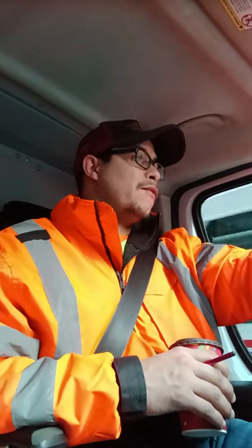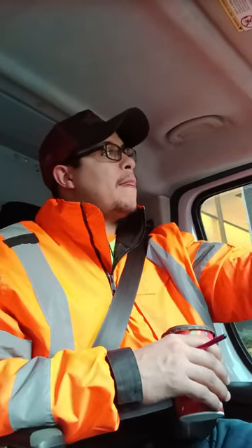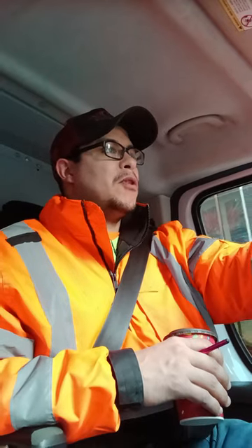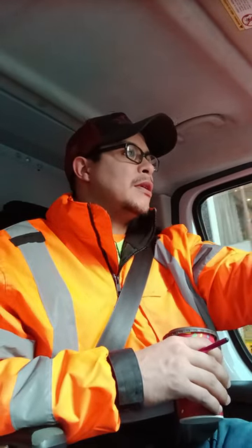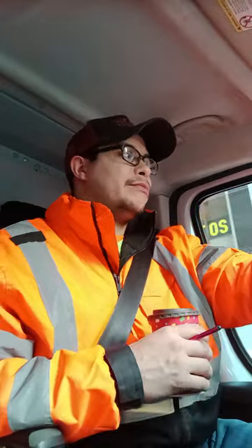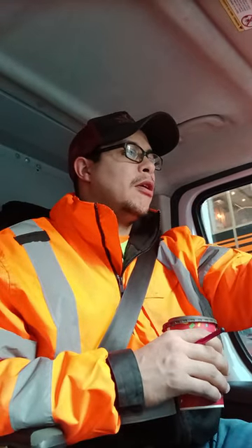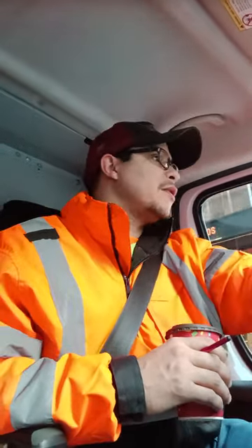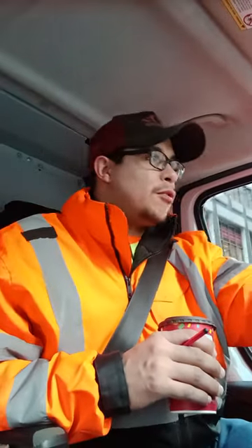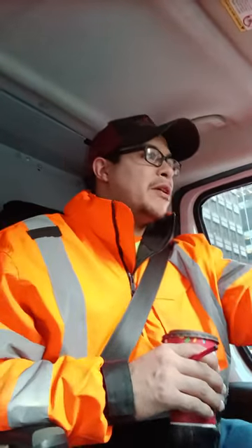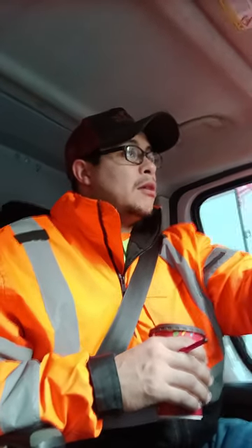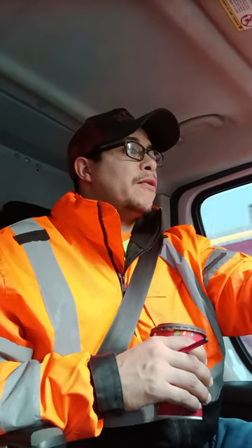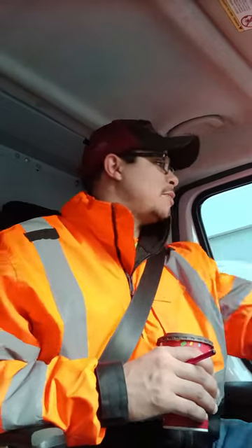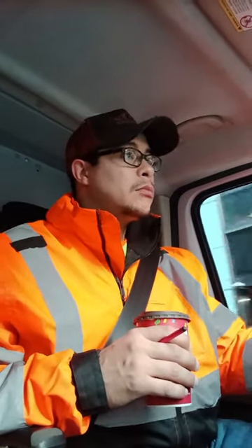Now, for mansions, okay, I get a lot of this because I've been questioned about this before by an apprentice. For mansions, look, you can do whatever you want. You can put arc-fault circuit breakers or GFCI circuit breakers for different rooms. Honestly, I like to make it convenient for the customer, and just put arc-fault receptacles, one per room. It has to be the first device into each room, living space.